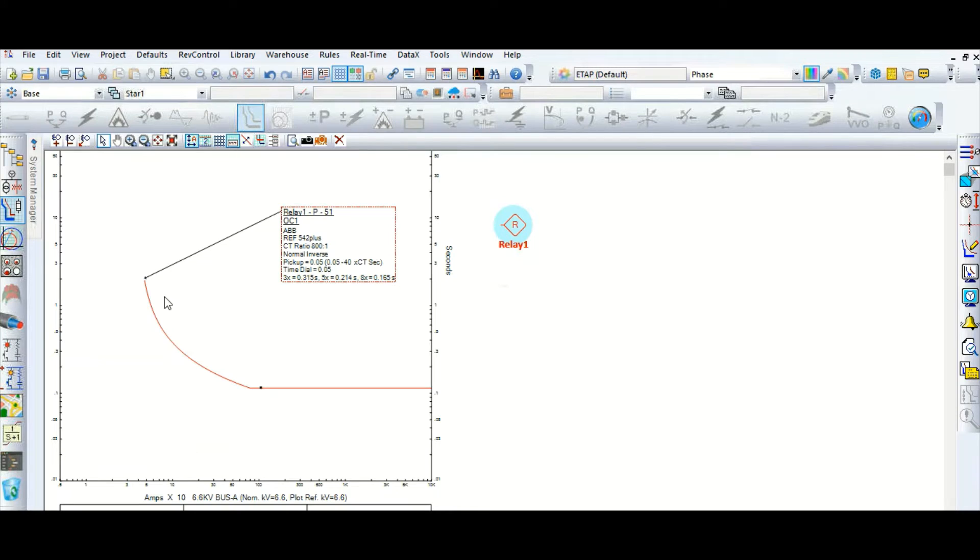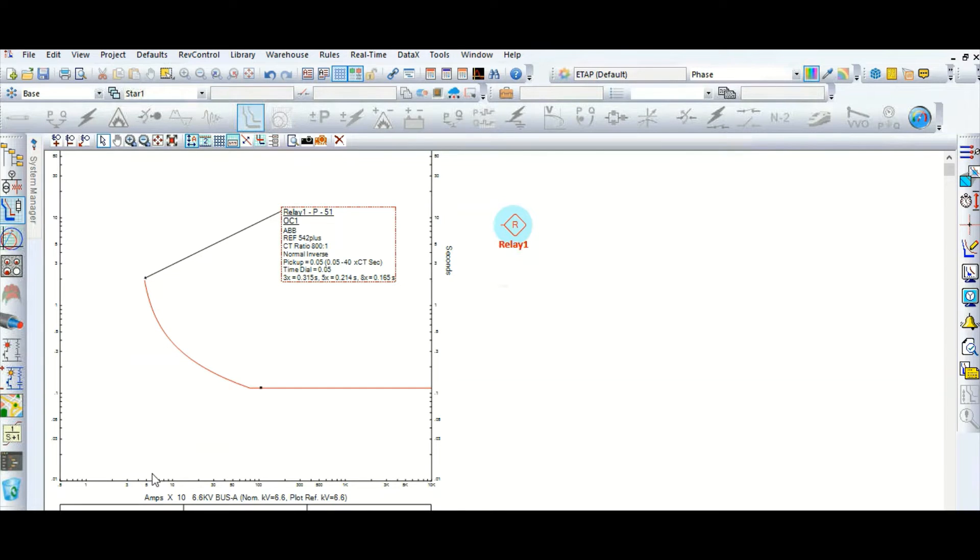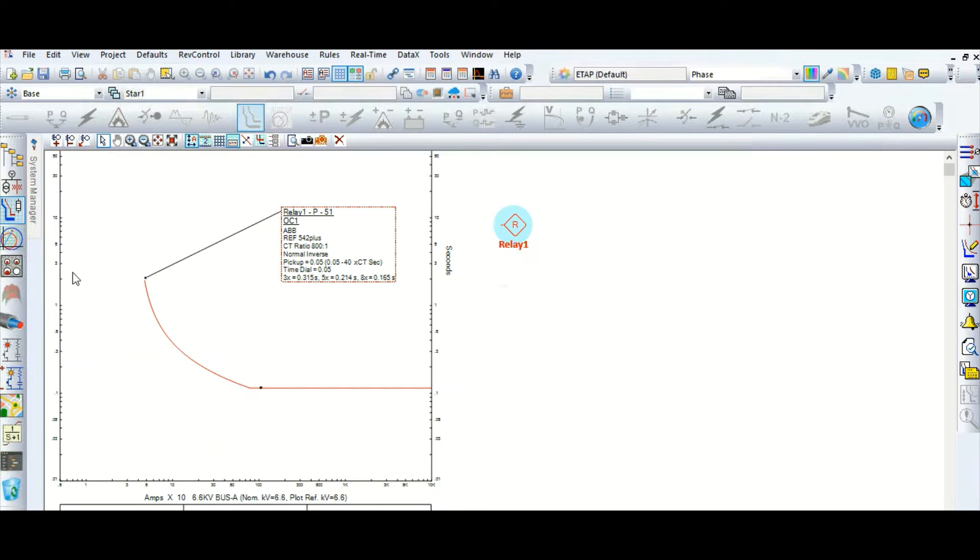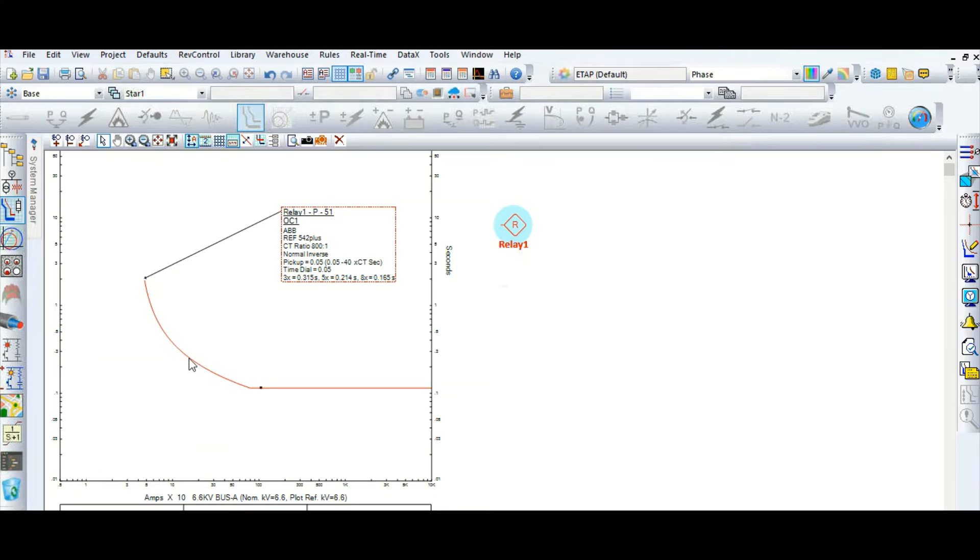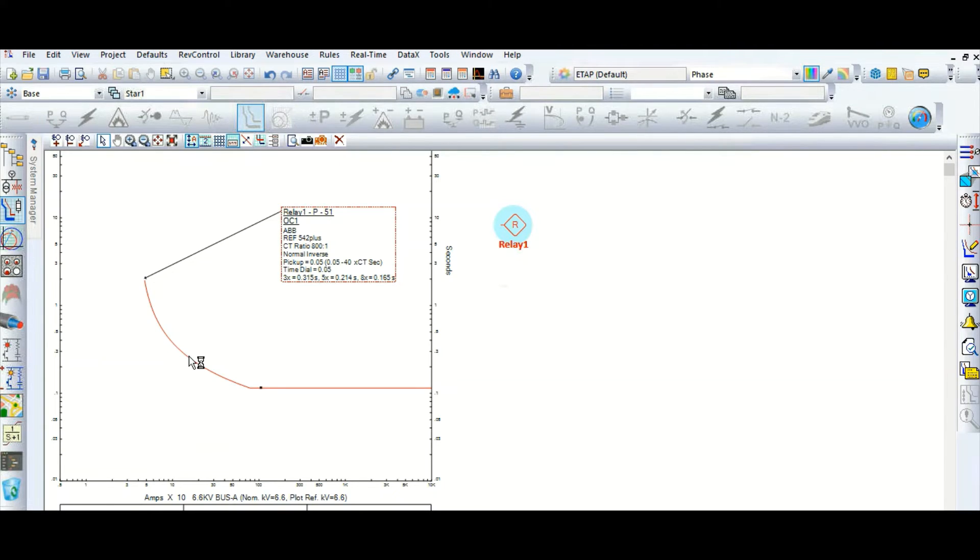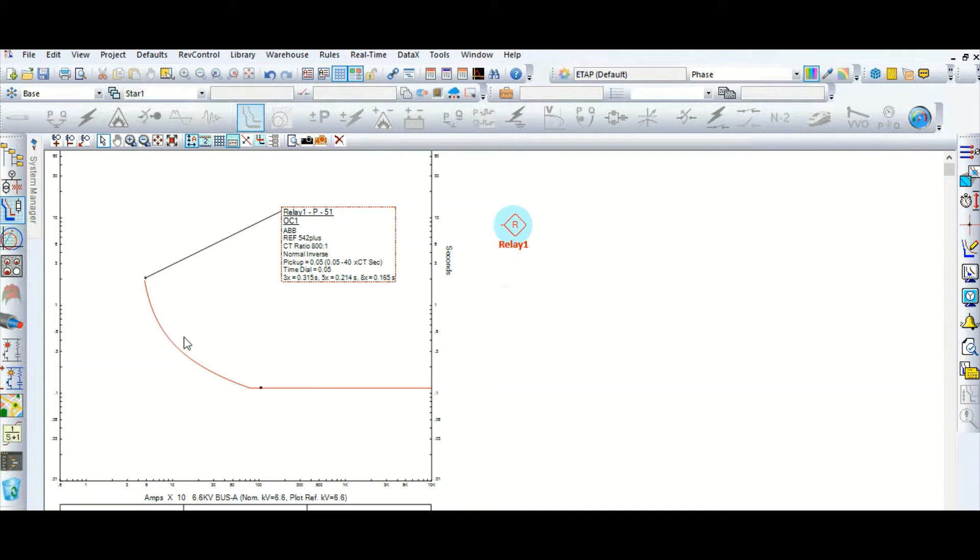Because it has the inverse current inverse characteristic. This X axis is the current and Y axis is the time. That's why time current characteristic curve. This one is time current characteristic curve. With respect to time, this current will change inversely. So this is the relationship. Because of the nature of this inverse characteristic, this relay characteristic is known as inverse relay. So this is normal inverse.